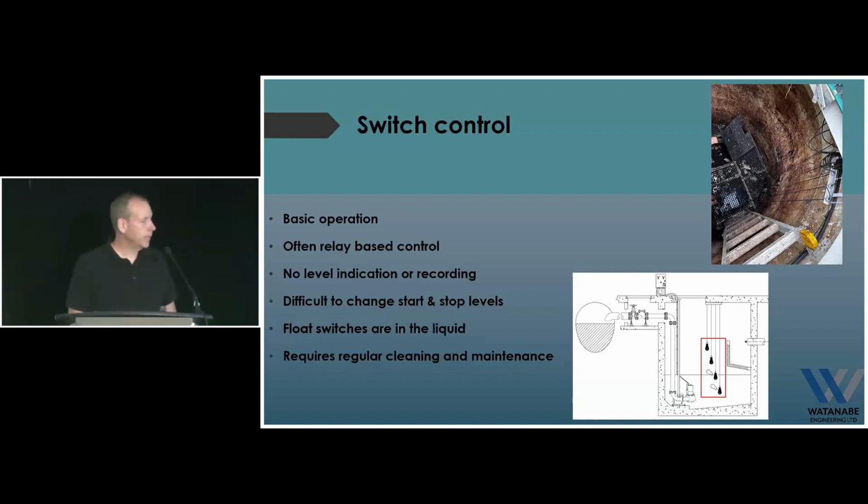I've been going around the province, seeing lots of different municipalities, First Nations communities, and I notice a bit of a similar trend. Some of these stations are not in the best shape, and what I tend to find is float switches, as you can see from the picture there. This is a station I was at fairly recently. They're not ever so well-maintained stations, perhaps, because you don't go to look at them too often. And part of the problem with the float switch, of course, is it's in the liquid.